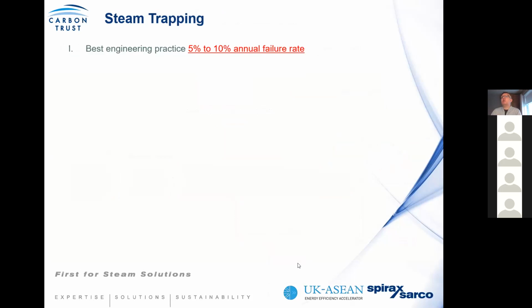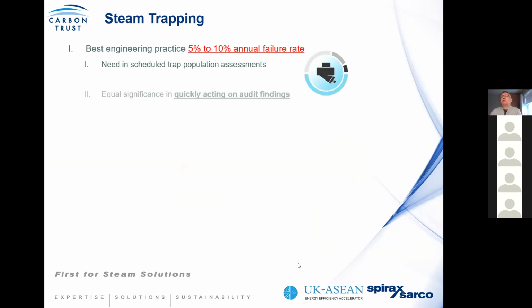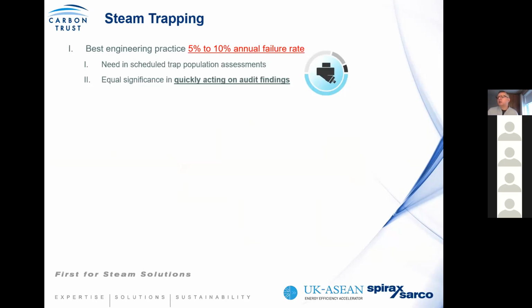So with steam trapping, again, we're talking about a 5 to 10% failure rate. There should be a scheduled trap population assessment at least once a year. Use external expertise, because this is a specialty in its own right. You need an engineer or technician with the expertise to understand when traps are working within their design parameters or not. Again, you need to look at how you can act on the findings. And like I mentioned with the STS-17, instead of just replacing a trap, look at what can be done to simplify future maintenance, because again, with best practice there's a 5 to 10% annual failure rate. So in other words, there's a likelihood that you might install a trap now, but you may have to go back to it in 10 years' time, for example.